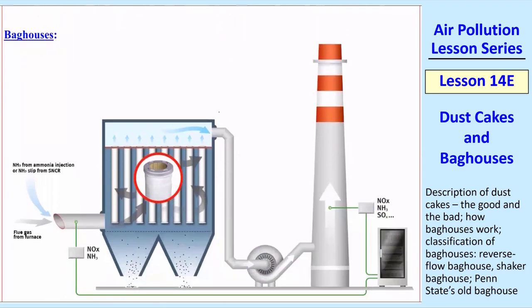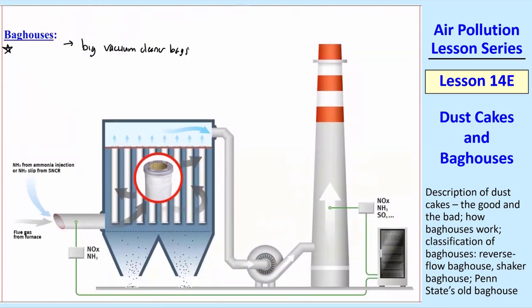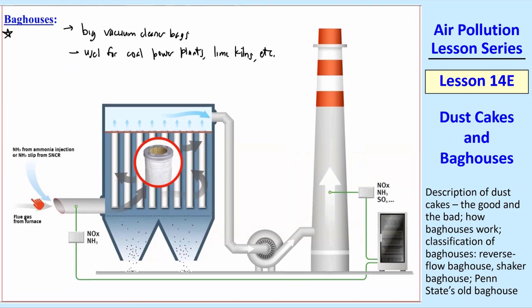Now I want to talk about bag houses. These are basically a whole bunch of big vacuum cleaner bags in a box. They're used for coal power plants, lime kilns, etc. Here's a schematic. The dirty air from the furnace comes in — in this case, the dirty air goes into the outside of the bag and goes through it. Then the clean air comes out the inside of the bag at the top and goes up the stack through a blower. But a dust cake will build up on the outside of these bags, so each of these bags starts building up this dust cake.